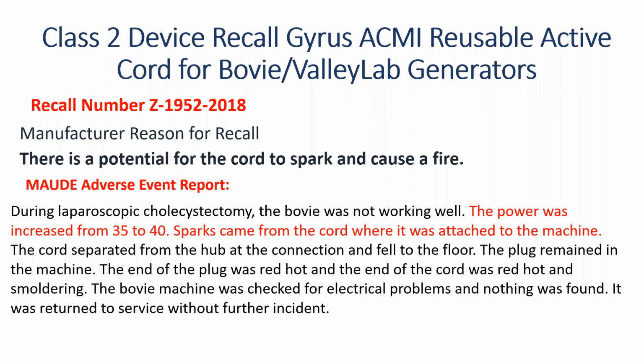So in one of those MAUDE reports, it said that during a laparoscopic cholecystectomy, the bovie was not working well. And obviously the surgeon said to increase the power. So the power was increased from 35 to 40 watts. A spark came from the cord where it was attached to the machine. The cord separated, similar to the photo that I'll show you from the hub, at the connection and fell to the floor. The plug remained in the machine. The end of the plug was red hot, and the end of the cord was red hot as well, and smoldering. The bovie machine was checked okay, and there was no problem found.